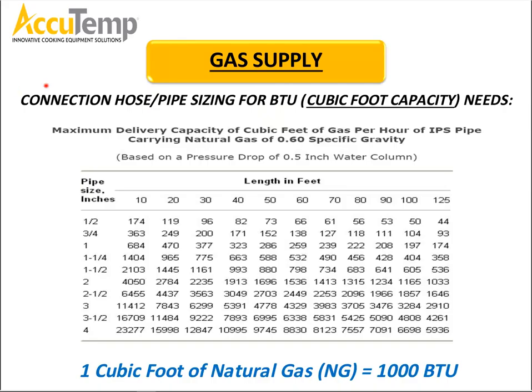All right, the first slide we're going to talk about is gas supply. Not just AccuTemp, but pretty much any other manufacturer will tell you that before installing any gas equipment, the first thing that should really be done is, depending on where the equipment is being installed, to check whether there is enough gas supply to support the equipment based on the equipment's BTU rating.